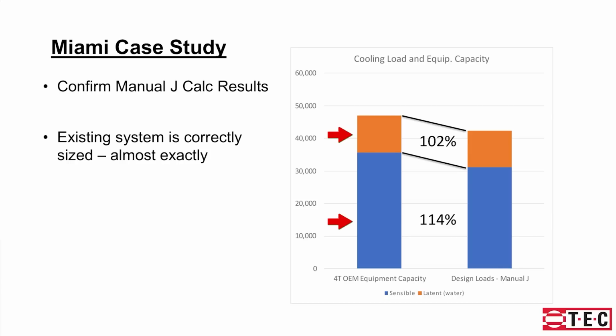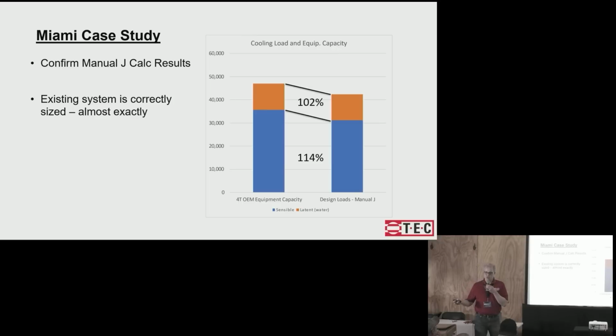Okay, so the technician in this case did the load calc and found out that this is what the house needs. The house needs this much latent and this much sensible. So the system's covering 114%, a little bit more than necessary of the sensible load, and just slightly more than you need on the latent load. So is this system sized correctly? And the answer is yes.